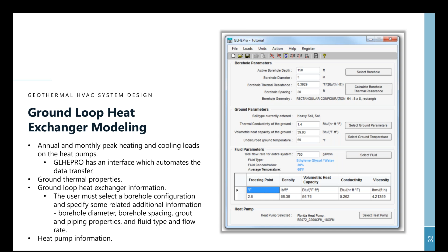Having accurate information for the equipment that you're going to use is extremely beneficial, because not every piece of equipment is rejecting heat or absorbing heat from the heat exchanger in the same way. So the modeling software is quite sophisticated, and it can look at the performance curves for various pieces of equipment and match that with the geothermal heat exchanger design.